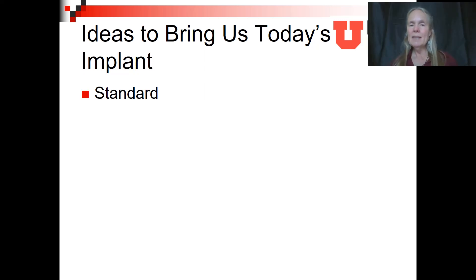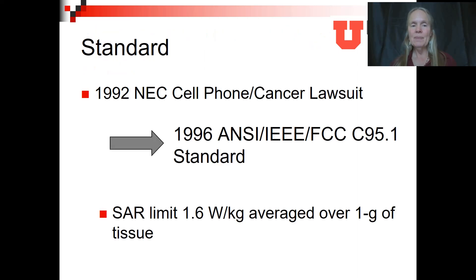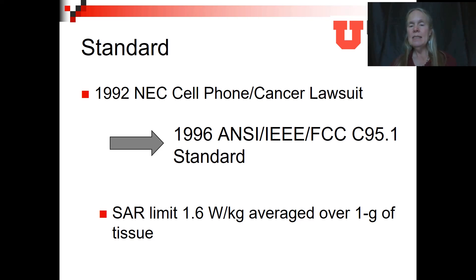There are several important ideas that bring us today's implant. The first one is a standard. We needed several types of standards, one of which is how much power can be deposited in the body safely. In 1992, there was a cell phone cancer lawsuit where a woman had been holding a cell phone against the left side of her head and had gotten a brain tumor there. This resulted in a lot of research, and in 1996, the ANSI IEEE FCC C95.1 standard for specific absorption rate was established.